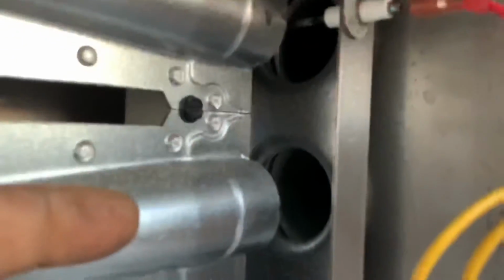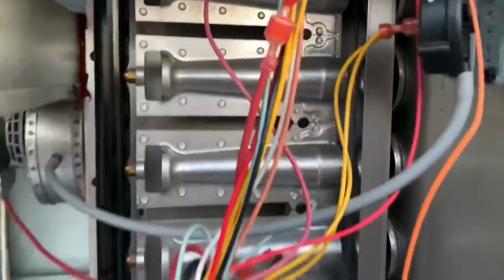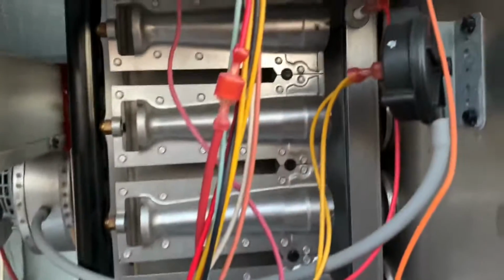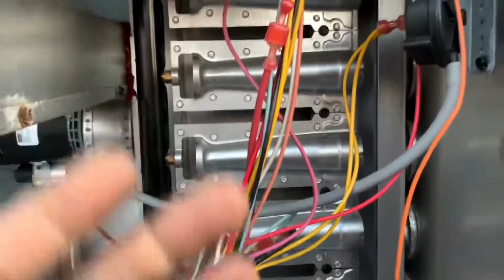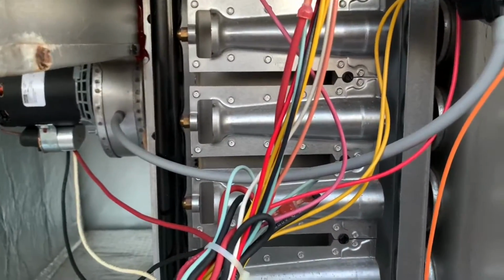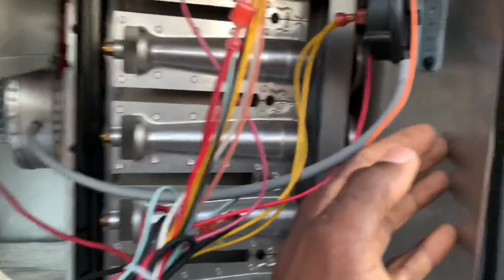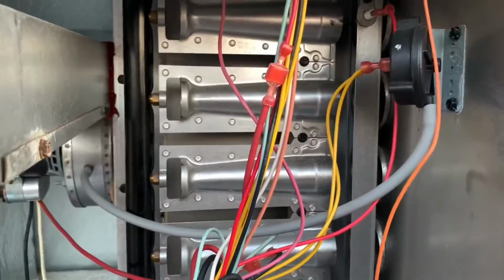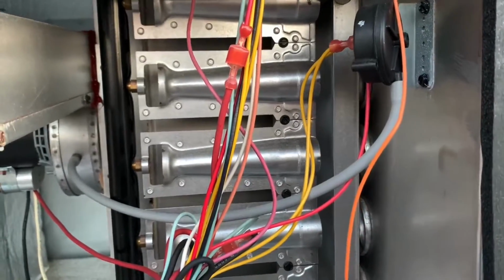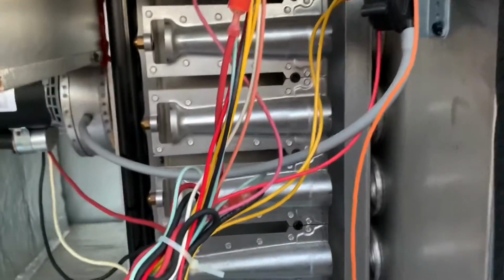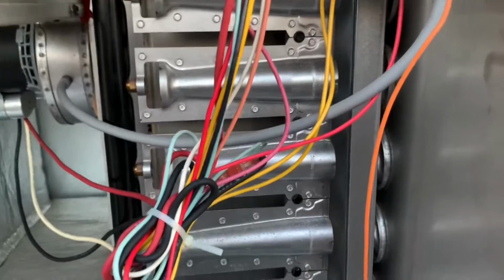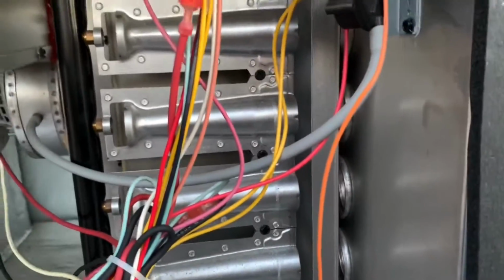The fire goes in straight and through into those tubes, right? Into the heat exchanger. All right, so that's what that does. If the flame is rolling out, this could be very dangerous, because if the heat exchanger has a hole in it, it could be leaking carbon monoxide into the conditioned air, or into your home, or into your rooms, or into your jobs, wherever this unit blows air.